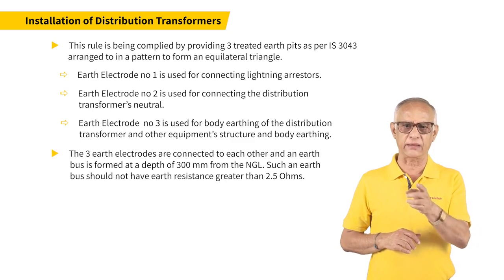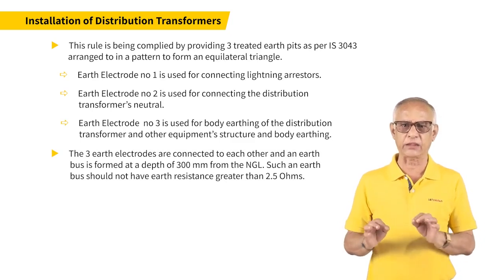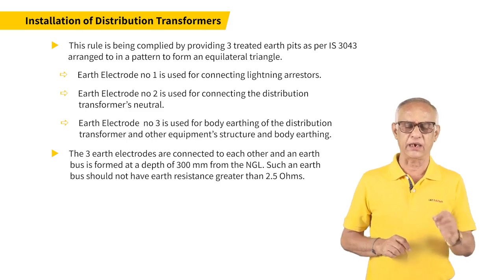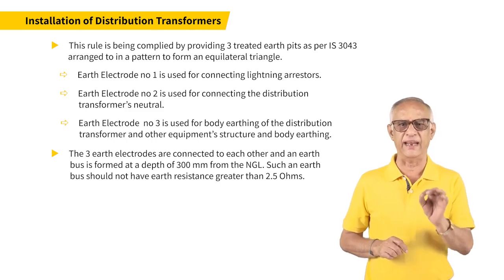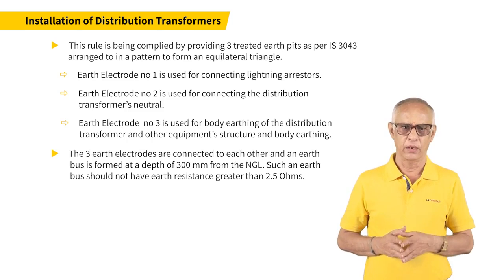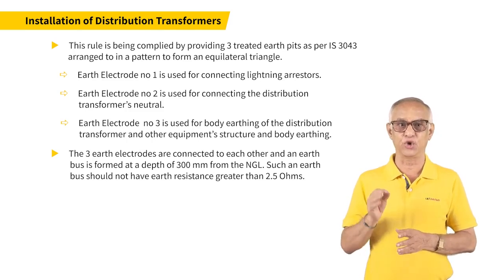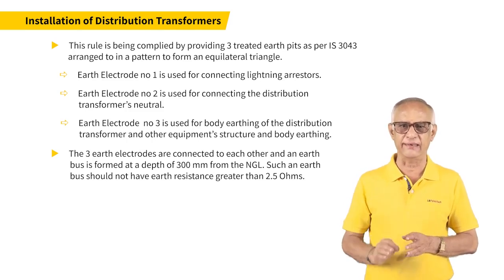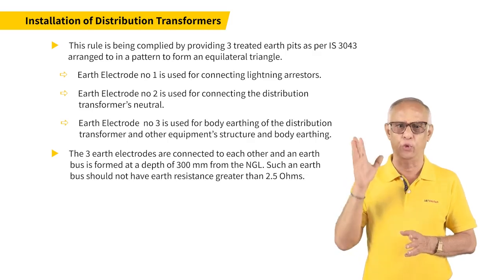The 3 earth electrodes are connected to each other and an earth bus is formed at a depth of 300 mm from the natural ground level. Such an earth bus should not have earth resistance greater than 2.5 ohms.